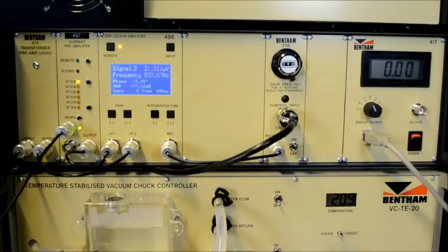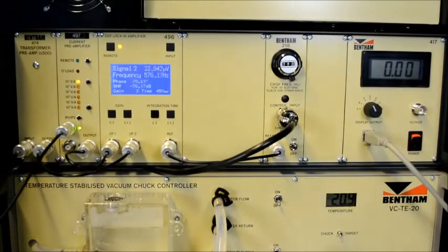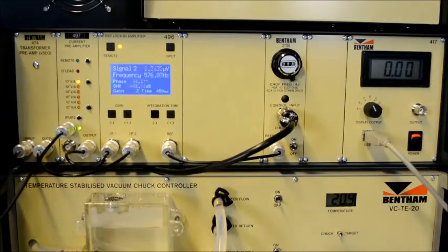In the case of the 497 AC mode, one has scope, should one require, to change the chopping frequency applied. Whereas in use of the 474 transformer, one should always maintain 580 Hz chopping frequency, and certainly not a harmonic of mains. In the 497 AC mode, not using the transformer, one has scope to reduce the chopping frequency if required.